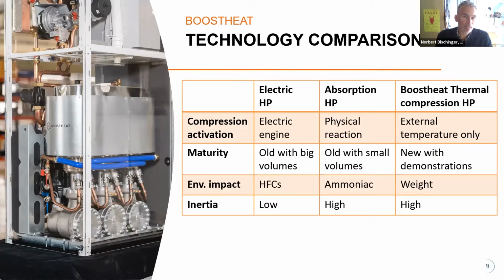Let's say the key differentiator regarding absorption heat pumps, which are sometimes also mostly thermally driven, then electric heat pumps: in our system, we are just using external temperature without a solvent, so no physical reaction inside, and we're not depending on the available electricity power on the grid. On the other hand, we cannot feed in PV electricity. This is an issue. We have a small electric consumption, which is in the range of that of a conventional condensing boiler. Our product is not yet available in large volumes. We are manufacturing it on our assembly line. We have, as you've seen, around about 80 installations so far. We are coming up with a second generation now.